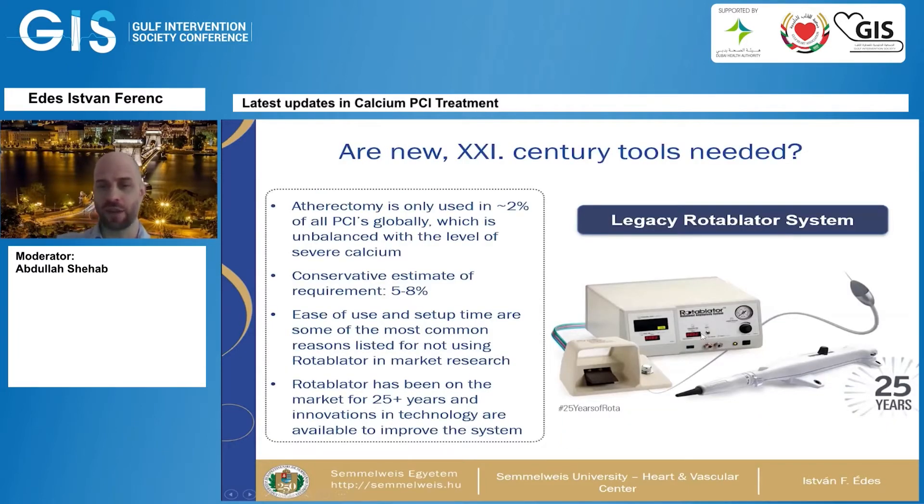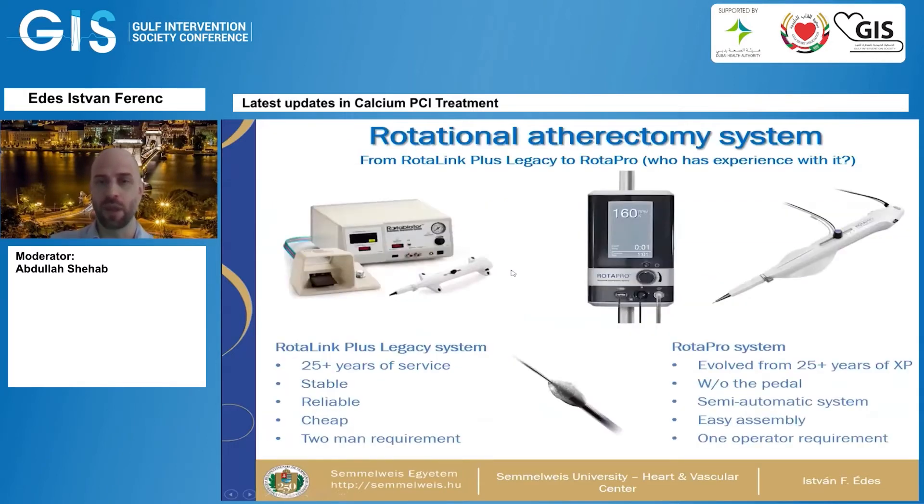The legacy rotablator system you see here is more than 25 — actually almost 30 — years old. It is underutilized despite being an extremely stable and very good system, especially given the extent of calcific coronary artery disease we see. The new system is the RotaPro, replacing the older RotaLink Plus. It is without a foot pedal — which was a real nuisance — it's a semi-automatic system, very easy to assemble, and only requires one operator, so you don't even need a dedicated nurse as was absolutely required for earlier iterations.